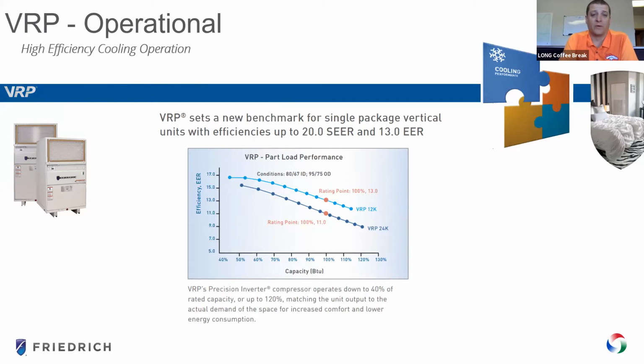So with the VRP, you're able to slow that compressor down to match the cooling load or heating load that you have without providing more than you need, which is how we're able to drive our part load efficiencies. Another benefit is that we're able to overdrive these compressors about 20%. So if you do happen to have a design day, or a day that even exceeds what you're expecting, that extra 20% that this compressor has will help get you through that in a comfortable space without sacrificing it.